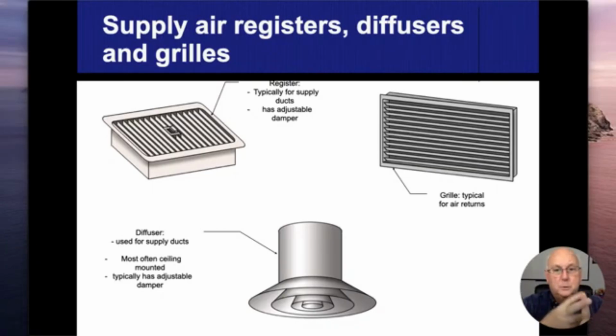Registers have dampers. Grills do not. Diffusers are going to be typically in the ceiling. Registers are typically going to be on supplies. Grills are going to be typically on returns. And diffusers are going to be typically on supplies.